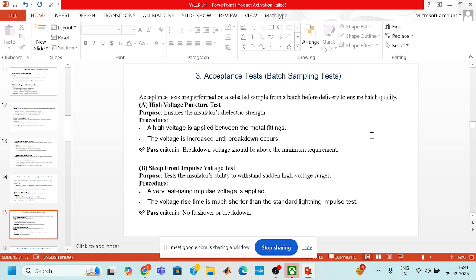Now, the third test is the acceptance test, also known as the batch sampling test. Acceptance tests are performed on a selected sample from a batch before delivery to ensure batch quality. In this, there are two types of tests: the high voltage puncture test and the steep front impulse voltage test. The high voltage puncture test is used to ensure the electrical insulator's dielectric strength. A high voltage is applied between the metal fittings, and the voltage is increased until breakdown occurs. If the breakdown voltage is above the minimum requirement, then the insulator will pass the high voltage puncture test. Second is the steep front impulse voltage test.